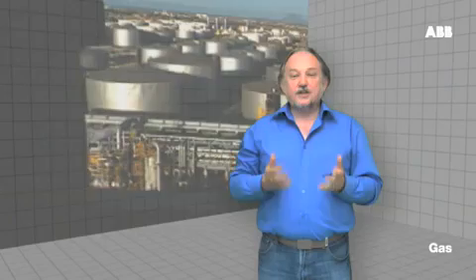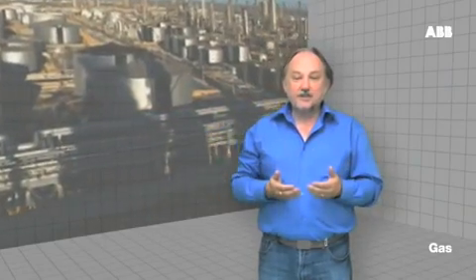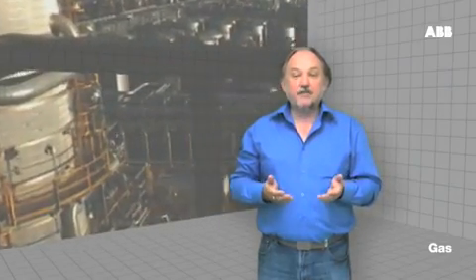It is imperative to determine whether any gas figures you are talking about are being considered in normalised units, standardised units, for example standard cubic feet or SCF, or in fact actual units of the pressure and temperature conditions that exist in the plant.